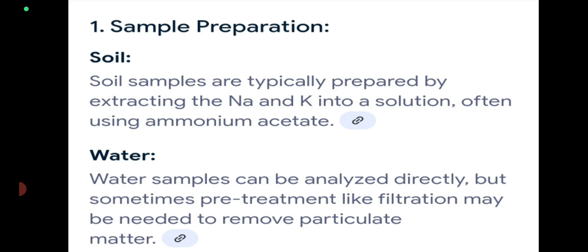Second one, flame emission spectroscopy. Nebulization. The sample solution is nebulized or atomized into a flame using an air-acetylene or air-propane flame. Excitation. The sodium and potassium atoms are excited in the flame, causing them to jump to higher energy levels. Emission. As the excited atoms return to their ground state, they emit light at specific wavelengths, characteristic of Na 589 nanometer and potassium 766 nanometer.